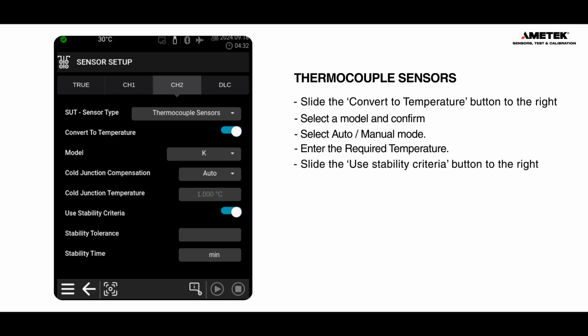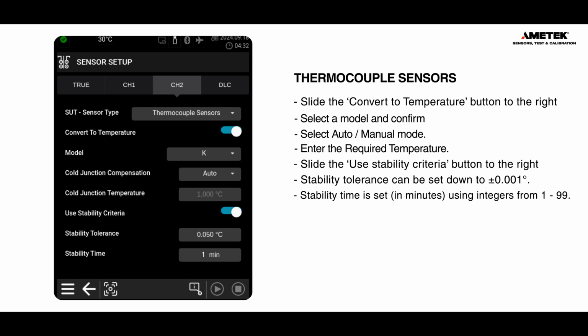Use stability criteria. When activated, stability is checked on both the reference sensor and the sensor under test. If not activated, only the reference sensor is monitored for stability. Stability tolerance. Set the stability tolerance using the numeric keys, with values as precise as plus or minus 0.001 degrees. Consider the expected performance of the sensor under test before choosing the tolerance. Stability time. Set the stability time using the numeric keys. You can choose a duration from 1 to 99 minutes.